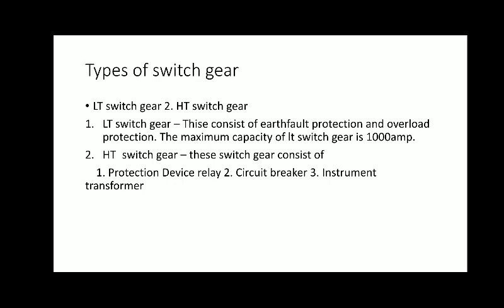Okay, next one, it is a HT switch gear. These switch gears consist of three parts or three things. That is first one, a protection device relay. Second one, circuit breaker. Third one, instrument transformer. So the protection device relay, that is 2 number of overcurrent relay and 1 number of earth fault relay fed with a battery circuit of 24 volt. 2 number of overcurrent relay are there and 1 number of earth fault relay are there.